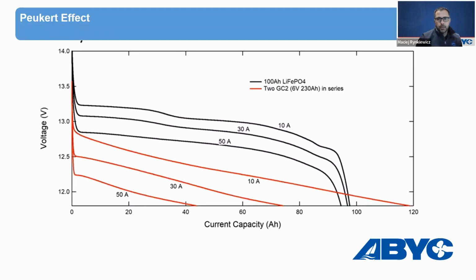Now we have the Peukert effect. Basically, as the rate of discharge increases, the battery's available capacity decreases. So your typical 100 amp-hour battery might be rated for 100 amp-hours at, let's say, a 5 amp load. But when you try to draw like 50 amps from the same battery, the capacity will be much lower. We can see that on these red curves here.